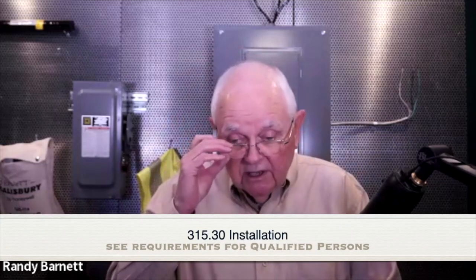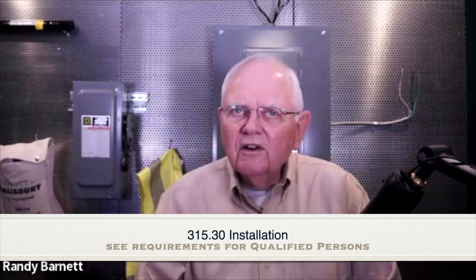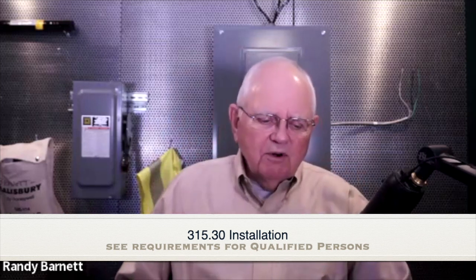So when it comes to terminating and splicing these cables, there are some very specific requirements, because if I mess it up, this cable will fail. And I don't want medium voltage cables to fail. They usually play a big part in my distribution system, don't they? So if I take a look at the requirements for installing this cable, I go to Article 315, Section 30. So it falls under Part 3, installation. And 315.30 says I have to be a qualified person.